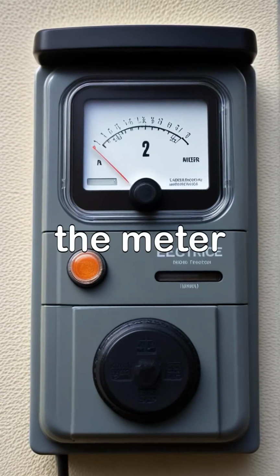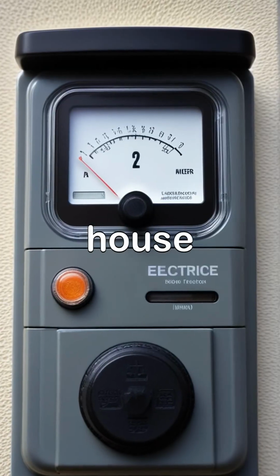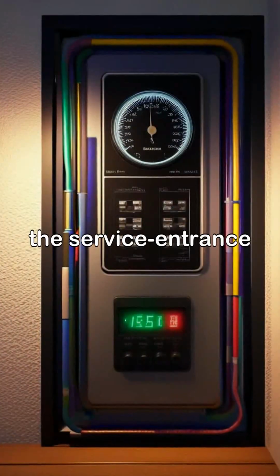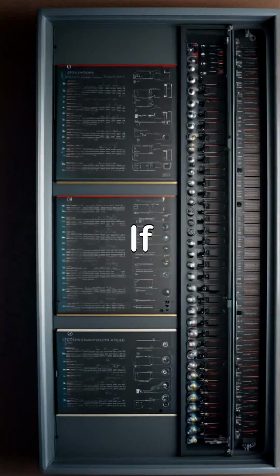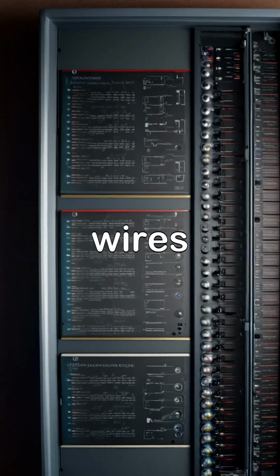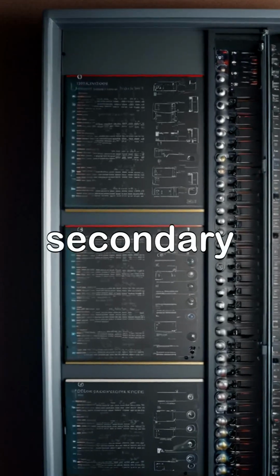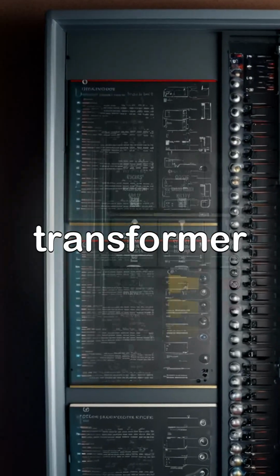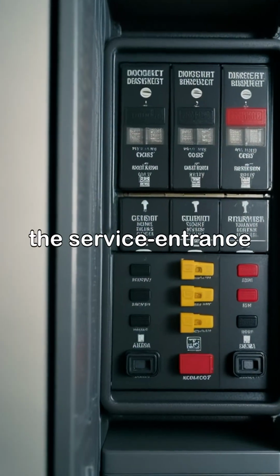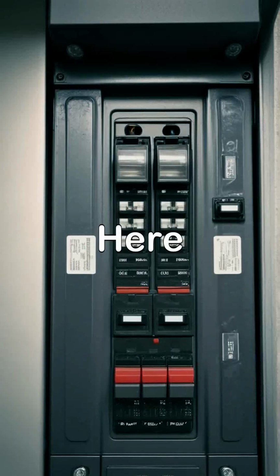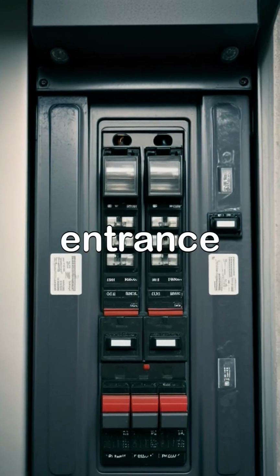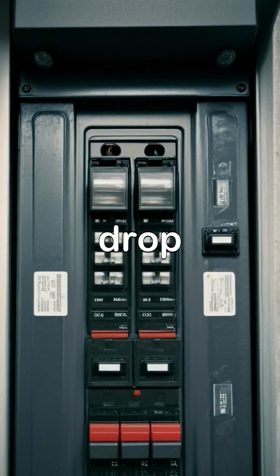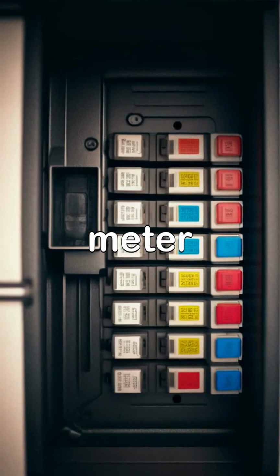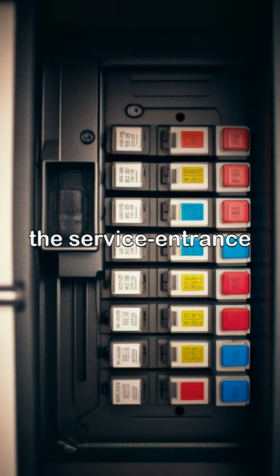They then enter the meter, which is mounted on the outside of the house, and continue on to the service entrance panel inside. If the house has overhead service, the 3 wires, called the service drop, extend from the secondary side of the distribution transformer to a point near the service entrance head at the top of the service conduit. Here they are spliced to the service entrance conductors, which enter this head, drop down through the conduit into the meter, and continue on into the service entrance panel.